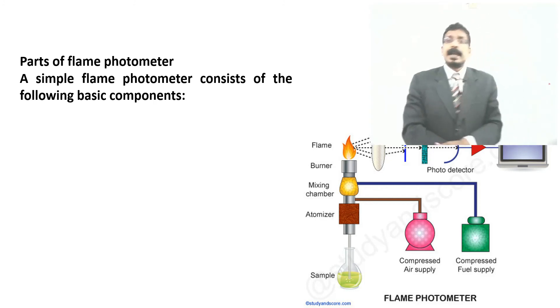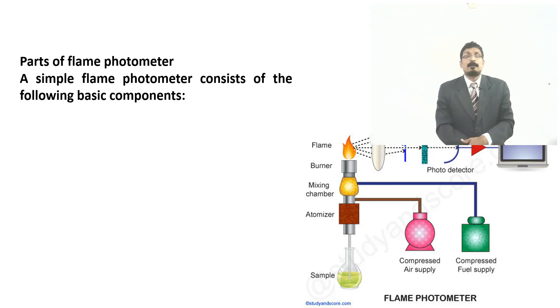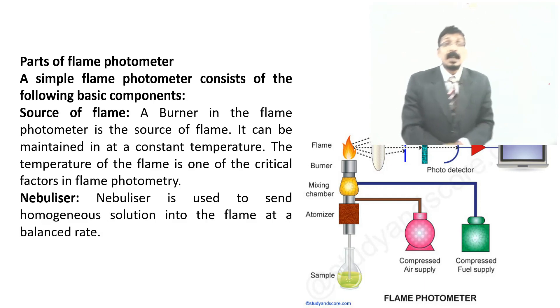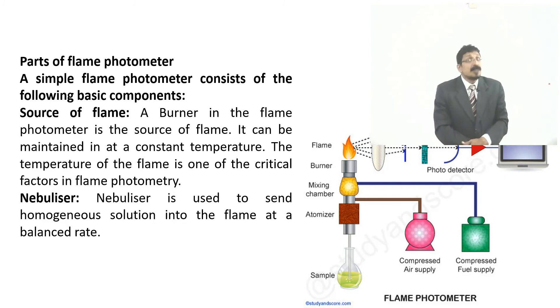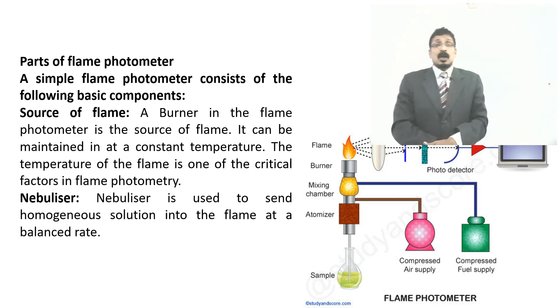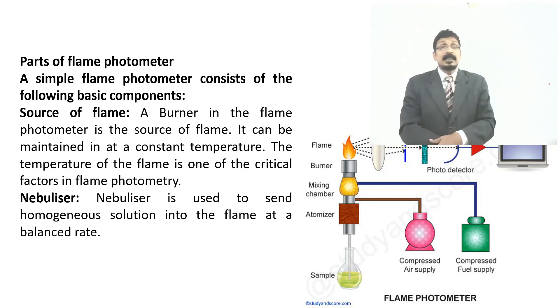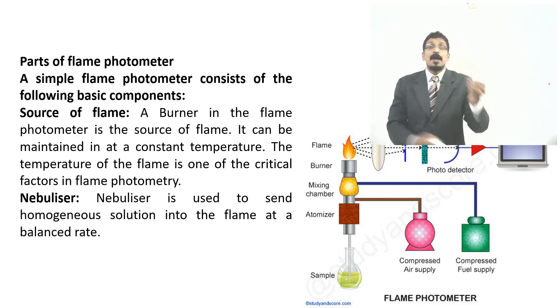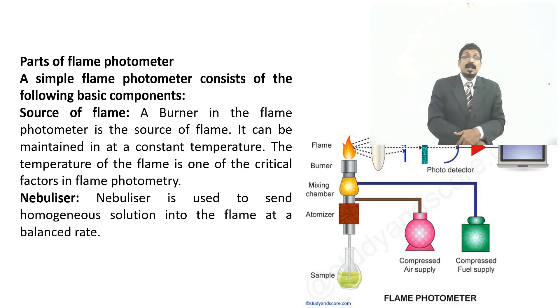A nebulizer takes the sample through a capillary tube; compressed air through the nebulizer sprays a homogeneous solution into the flame at a balanced rate. The optical system — the detector system — consists of a convex lens and a mirror. The mirror transmits light emitted from the atom, whether sodium or potassium, and helps focus the emission to the lens. The lens then focuses the light to the slit.